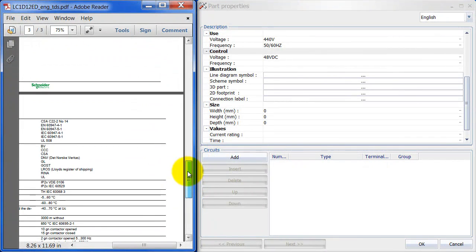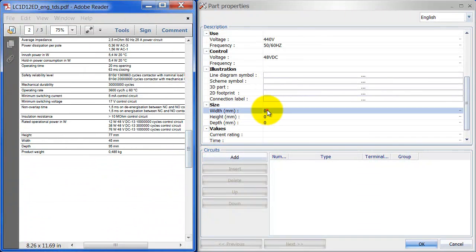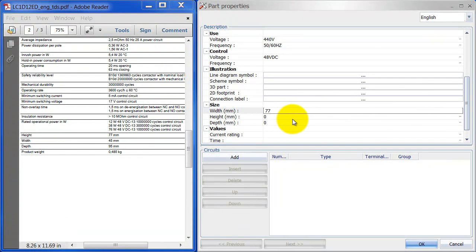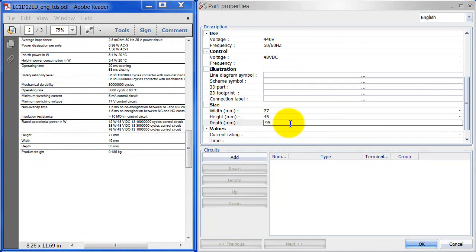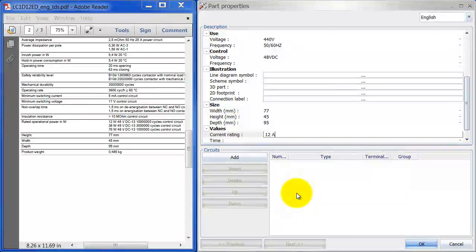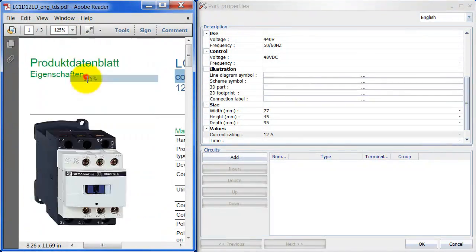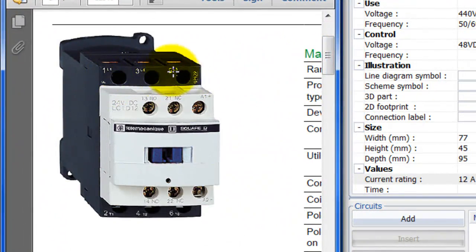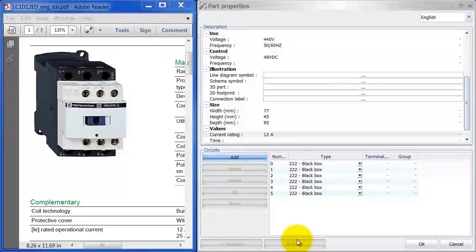I'll add some dimensions here — let me have a quick look. There we go: 77, 45, and 95. You can also add your current rating, which is 12 amps, and fill in any additional information you want. The important part comes down here where we're going to add circuits. As we said, I can see one, two, three, four, five, six circuits on the datasheet, so I need to add six circuits here.